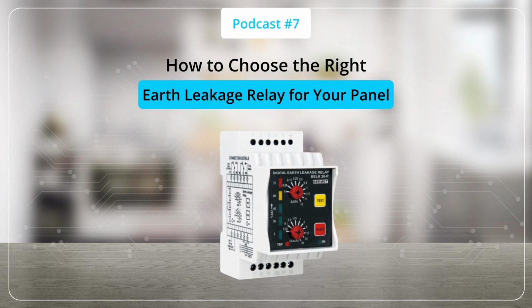Now let's understand what an earth leakage relay is and how it works. An earth leakage relay is a safety device designed to monitor electrical circuits for leakage currents. It operates together with a zero-sequence current transformer, often called a ZCT, or a core balance current transformer, commonly known as a CBCT. Under normal operating conditions, the current flowing through the phase conductors is equal to the current returning through the neutral conductor. However, when leakage occurs, a portion of the current flows to the ground instead of returning through the neutral path. This creates an imbalance.